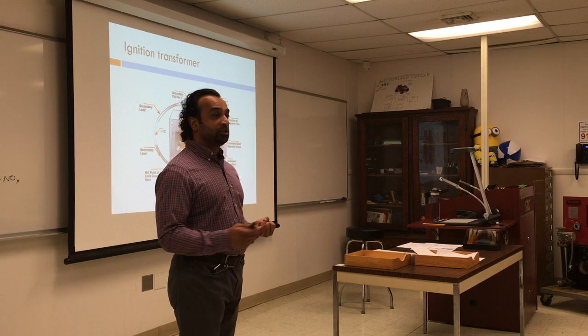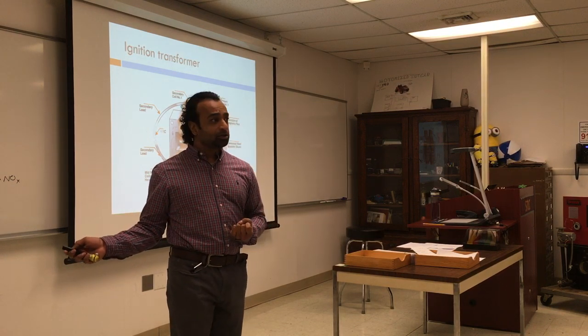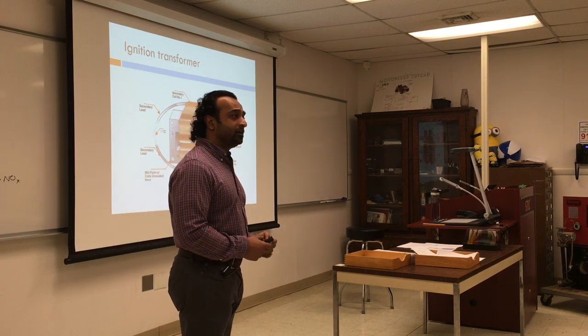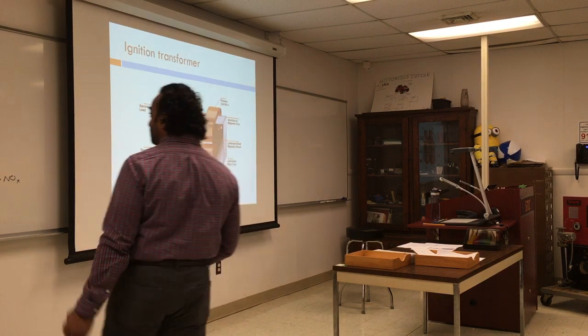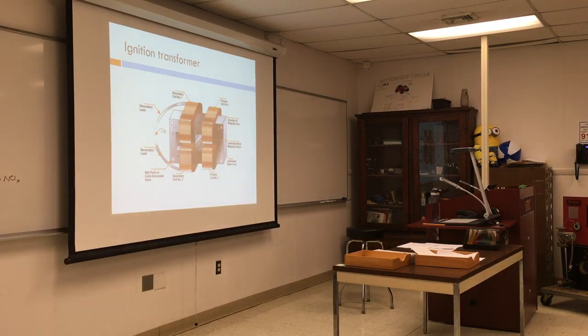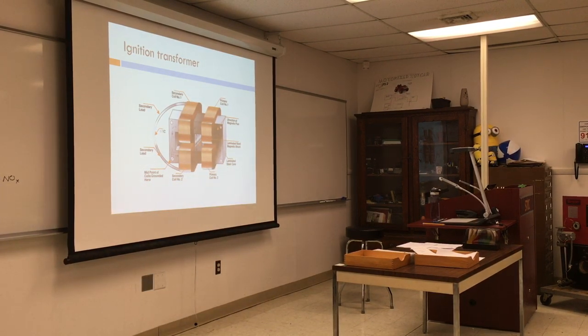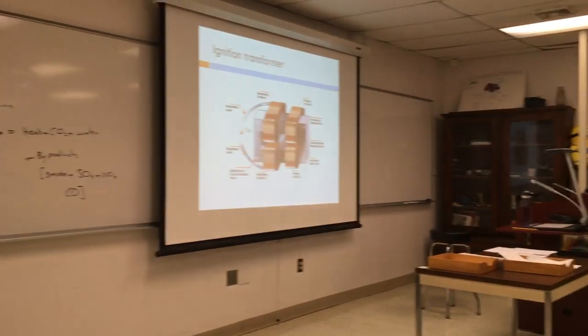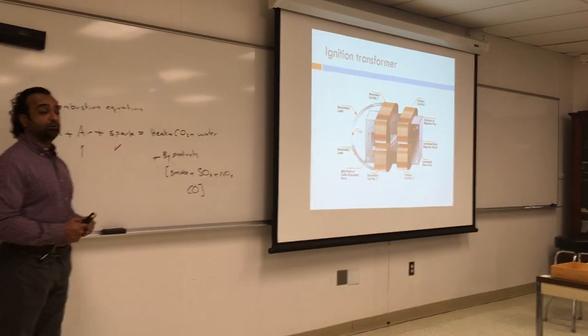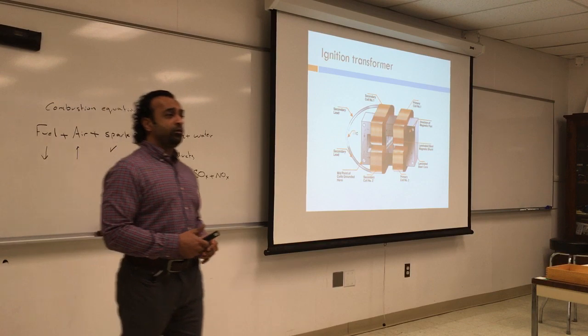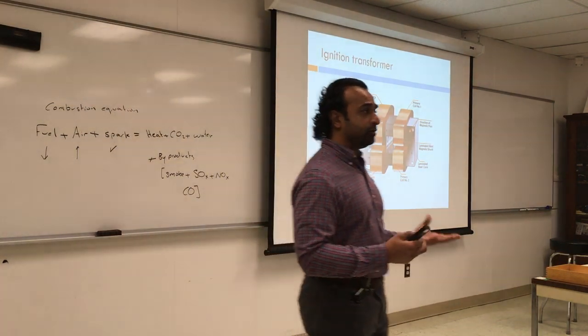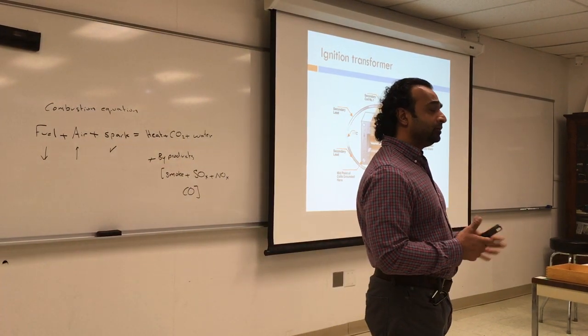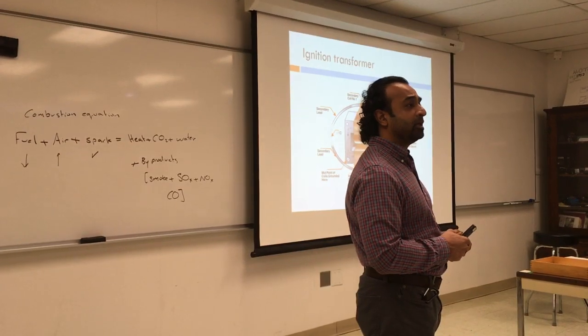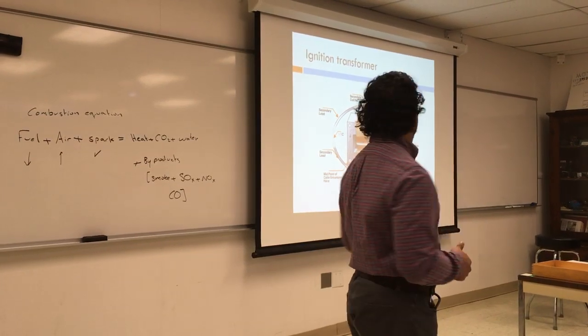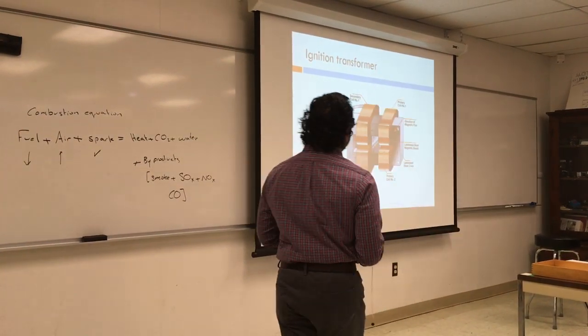So you have fuel, you gotta check your fuel line, your nozzle, you're gonna check your air intake, and you'll check your spark. So you have 3 things you have to always have at the right balance to have combustion, or complete combustion. So, that being said, when you do troubleshooting, make sure you have your elements correct. Then you can see why we're not getting flame. So it's good to think of that when you do troubleshooting.